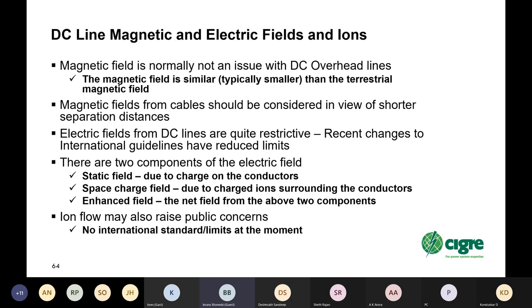One thing that also needs to be specified for the DC line is magnetic and electric fields and ions. Magnetic field is usually not an issue for DC overhead lines. Fields are similar to and typically smaller than the terrestrial magnetic field. Magnetic fields from cables, however, need to be considered in view of the shorter separation distance, because cables can typically be buried only a few meters underground. Electric fields from DC lines are quite restrictive, and recent changes to international guidelines have actually reduced limits, so it's become quite a lot harder to meet guidelines.